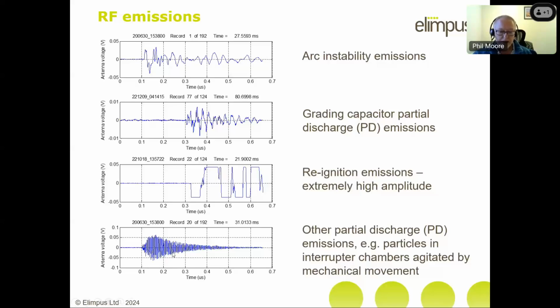The final signal there, and you can see this is much higher frequency, in the hundreds of megahertz, is a partial discharge from other parts of the breaker. What we tend to see is that when the breaker operates, if you get damage to the interrupters, there might be little bits of the nozzle that have been chipped away and fall to the bottom of the interrupter chamber. As the breaker operates, the mechanical agitation causes them to move around, and that can produce little bits of partial discharge. So it's similar to what you get in a GIS.